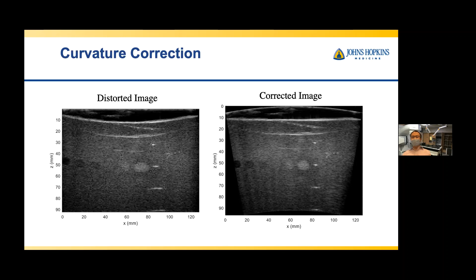So the ideal scenario is that we can do the image acquisition without any reflectors. So we developed a deep neural network that takes the raw channel data from the transducer, but does not use any shape information of the transducer. By simulating a large amount of raw data from the transducer with different curvatures and targets, we trained our neural network, and we were able to generate the images directly from the raw data. So here's the result of our recent published TMI paper.